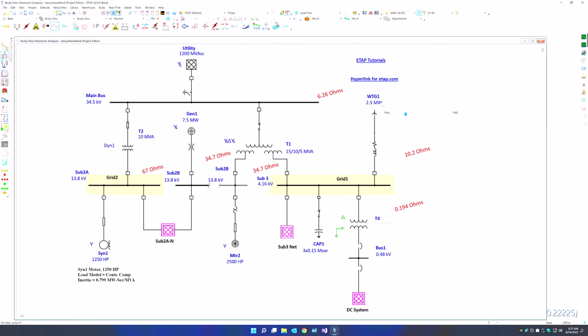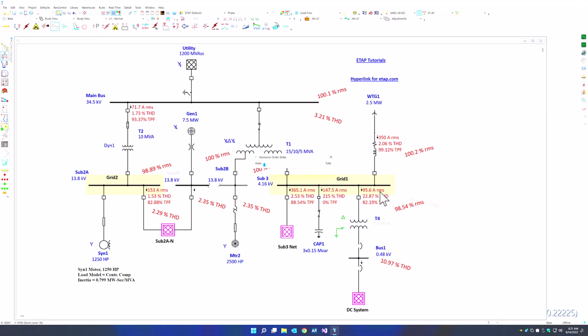sequence frequency scan. You can also run the harmonic load flow within ETAP, and the program essentially now gives you the current, total harmonic distortion, as well as the total power factor. The study report gives you the displacement power factor, which is the power factor in the system without harmonics, and the total power factor is giving us the power factor based on harmonic content within the electrical system. So this is the true power factor that we will be observing at the point of interconnection.